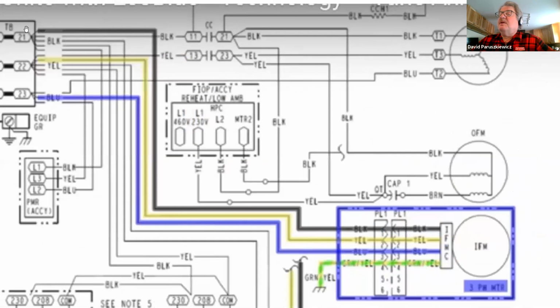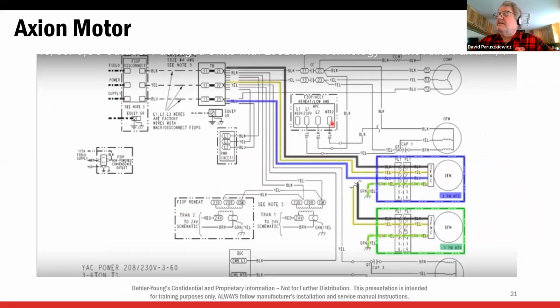And if I follow the wires, let's follow black, right to the motor. Yellow, right to the motor. Blue, right to the motor. So obviously that's a 3-phase. Down here is a single phase. It's just black and yellow. Same thing. We have power to this motor all the time. All right. So there should always be power to this motor. Also, there's nothing shutting this power off. So if you have power surges and stuff, that can cause a problem.